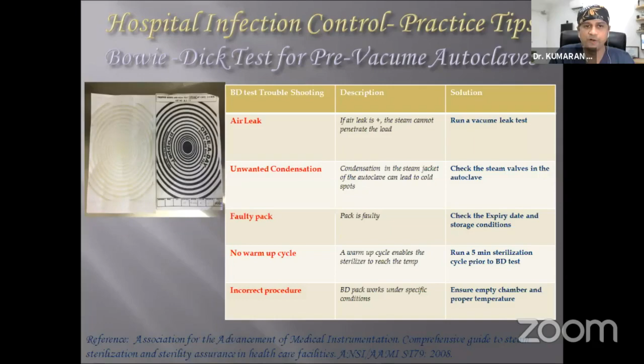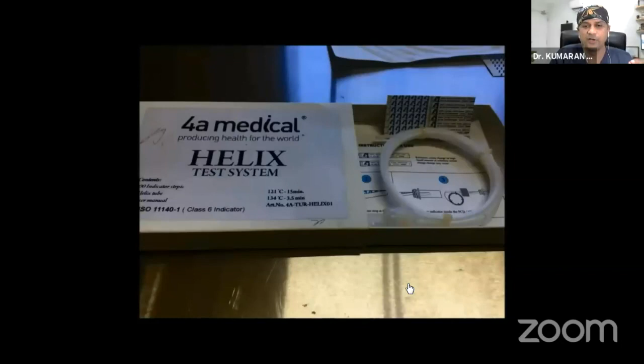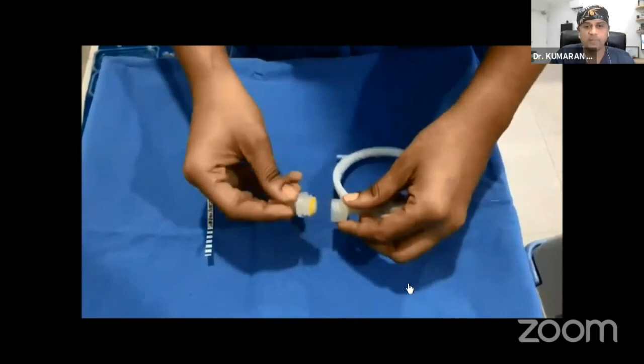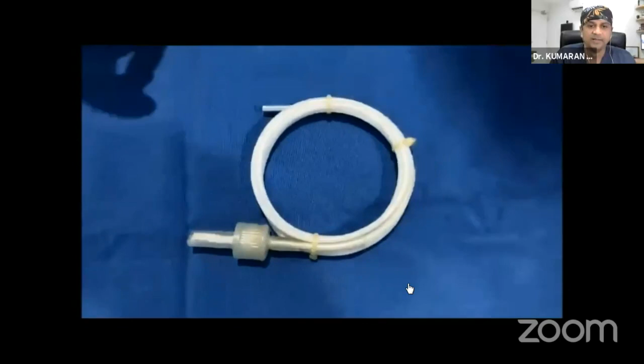So this is the class 6 indicator. So I'll finish in another 5 minutes. See, the class 6 indicator is very important whenever you have a hollow instrument. The most important thing and the common mistake done here is the way you fold the indicator. The indicator has to be folded inwards as shown here and not outwards, because most of the time if the indicator is folded outwards, the test is positive even with the initial autoclave cycle, before it gets completed. Then this should be packed as shown here.